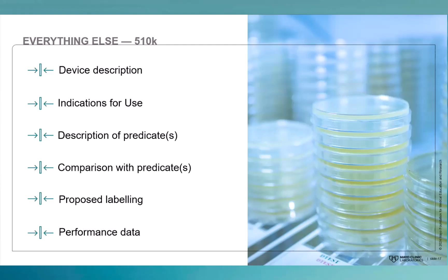For a de novo, again, device description, intended use. This is what FDA uses to really assess any medical device that crosses their desks. A discussion on controls. Remember, you need to talk about why you believe your test is not the highest risk. So what are you doing to mitigate that risk? Clinical data, this is a key difference. So clinical validity data becomes an important component of this. So not only can my test detect the analyte of interest, does it correlate with the disease of interest? Performance testing would be, again, your validation information. And then the other new piece is the benefit risk discussion. So here are the benefits of ordering the test, and here are the risks of ordering the test. And ideally, your benefits would outweigh the risks. Otherwise, there's a slim chance FDA would actually approve your device.